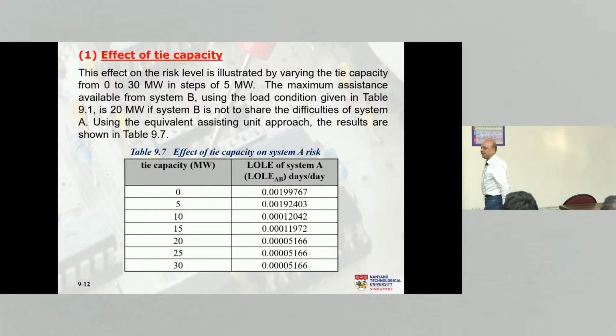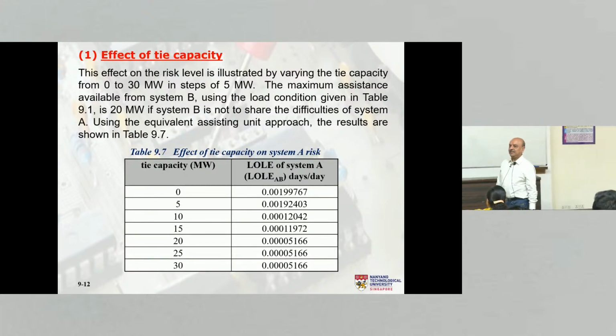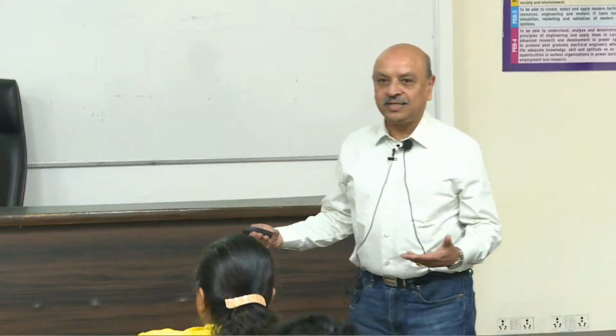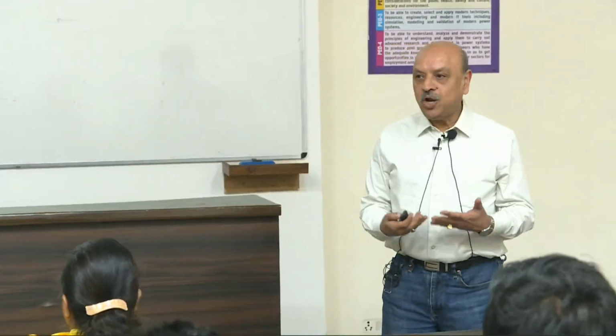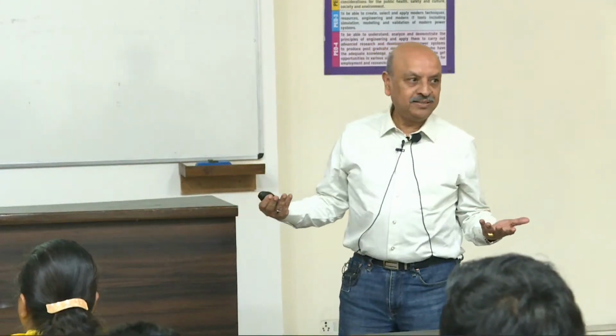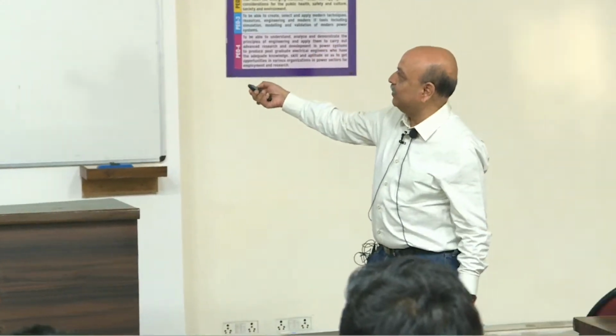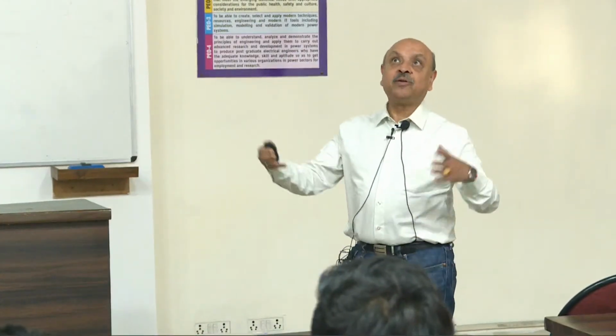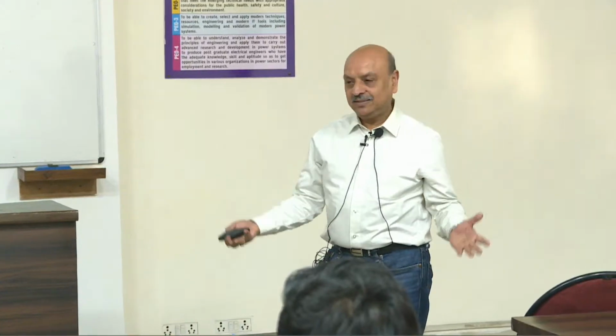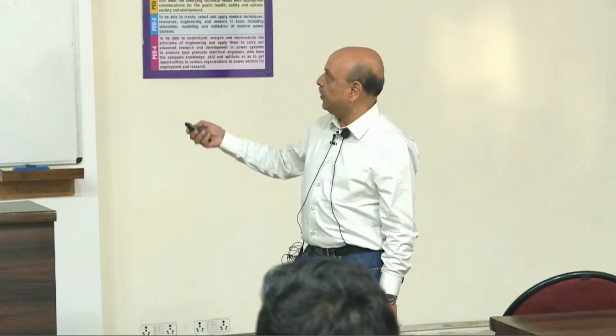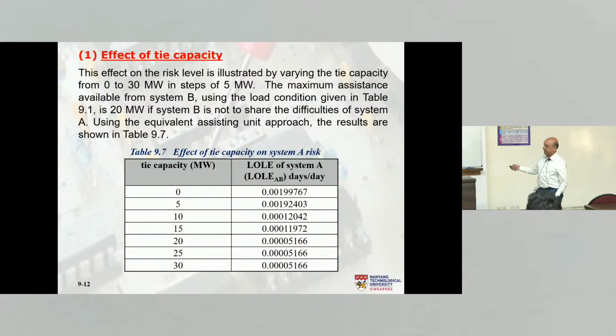Constrained by the capacity of the assisting system. Assisting system is 60 megawatt, peak load is 40. It will not help me beyond 20 megawatt. So beyond 20 megawatt, nothing will change. You put a 100 megawatt line, tie line capacity, it's not going to matter. It's just a waste, complete waste, okay? So we can do this calculation, and again, if you have the time, please try and do it.